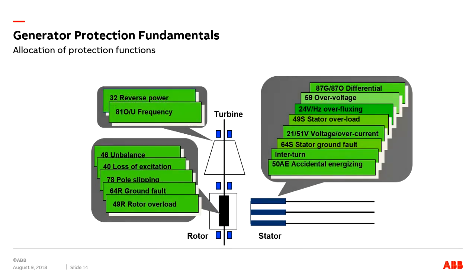Now looking at the different protections which are important for a generator. As we know, a generator has three parts which work together: the stator, the rotor, and the turbine. The protection functions are allocated to different parts of the generator. For example, the stator has protections allocated to it, like differential, overvoltage and so on. And then the rotor has different types of protection allocated to it. These protections are primarily to protect the rotor, and then for the turbine, it is reverse power and under and over frequency.